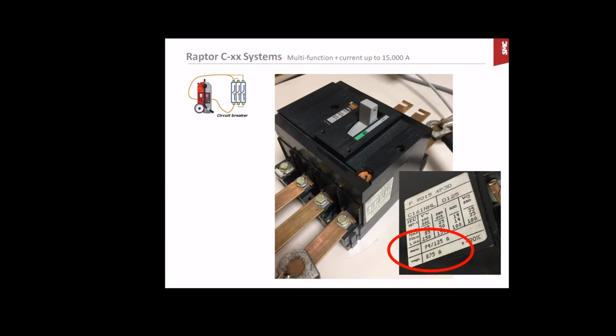You see that this breaker has two protection elements. One of those is the thermal sensitivity, which is now set up to 125 amperes, which means that any current below 125 amperes will not produce any tripping, no matter how long it is. But after that current, the tripping mechanism in the circuit breaker will start to operate, and it will start to time, searching for a thermal overload. So if the current exceeds this value, it will start timing before producing an interruption on the circuit.